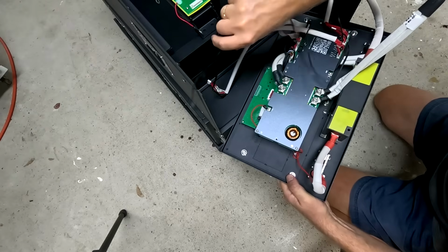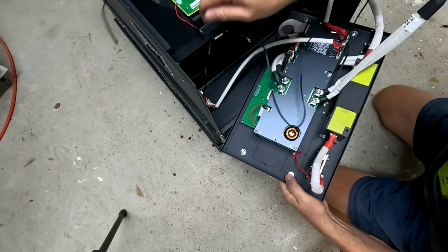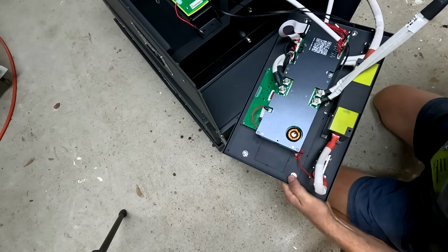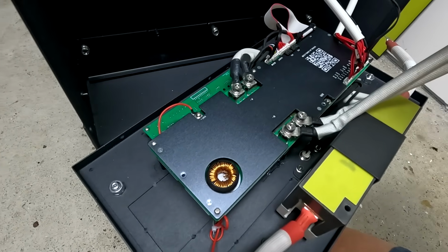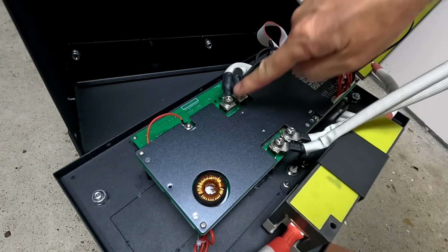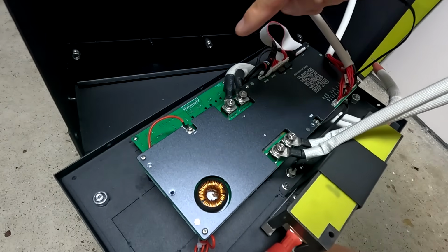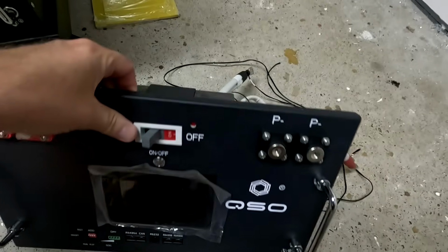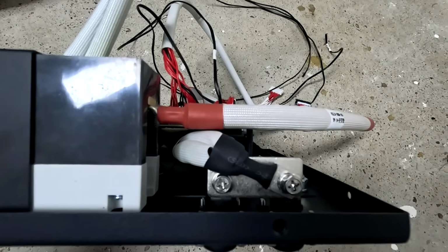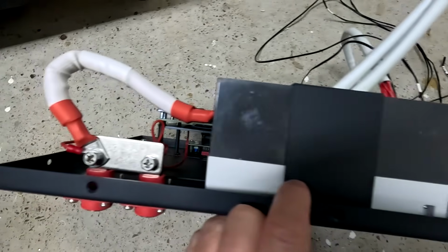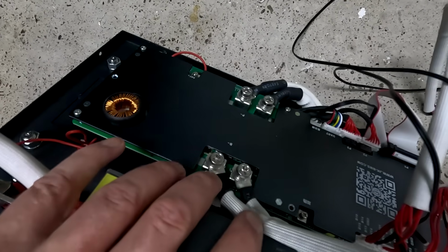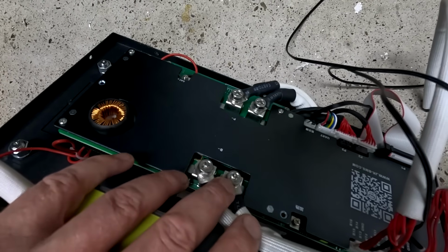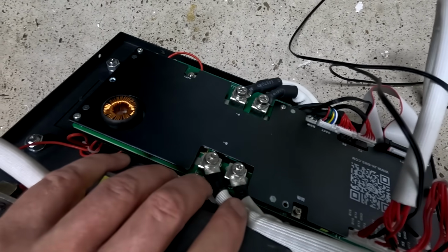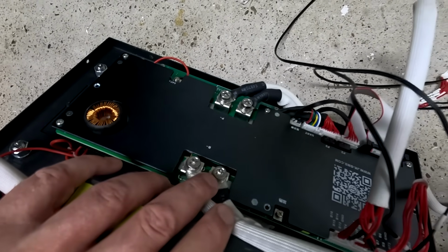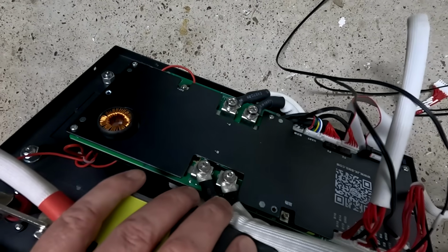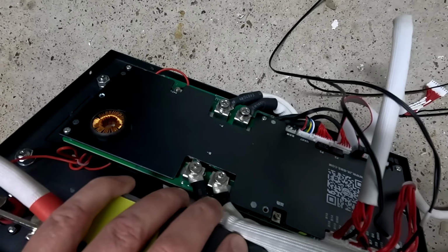Temperature sensors. 1 meter long temperature sensors just flying around. Okay. So obviously we have the JK inverter BMS here and the 2 screws telling us directly this is a 200 amp BMS. And what I also noticed is that none of the screws is actually marked. Even this is a pre-configured box. We cannot ensure that these connections are actually torqued correctly because it doesn't seem like someone has actually checked that. So no check marks. You have to check all the connections yourself.